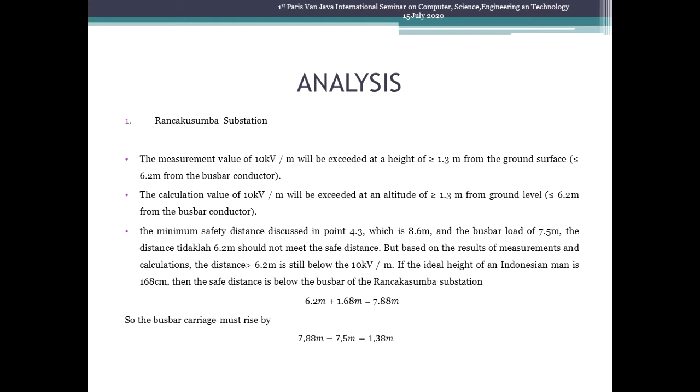The minimum safety distance discussed in point 4.3 is 8.6 meter, and the Busbar load of 7.5 meter, the distance 6.2 meter should not meet the safe distance. But based on the measurement and calculation results, distance more than 6.2 meter is still below the 10 kV per meter.